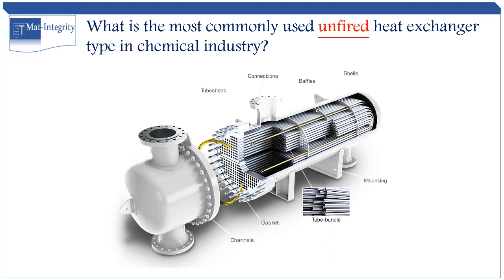The third component is a large cover connected to the shell via bolts and gaskets. This cover is known as the channel, and it is connected to the shell flanged end with the tube sheet underneath. Since the channel is open to the tubes, it also contains the tube fluid and is therefore considered part of the tube side.